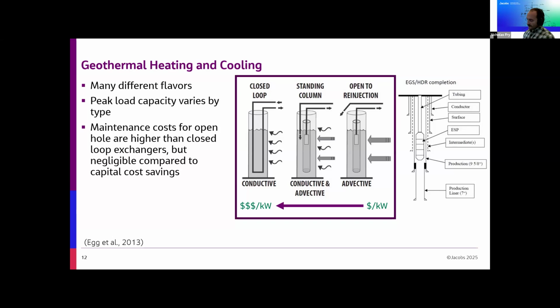Some differences: you may have casing in unconsolidated zones for geoexchange, but it's preferable that grouted completions, like the conductive borehole heat exchangers on the left side of the screen, are fully grouted from the bottom of the hole to the top. There are some open loop completions as well. What happens is the cost to the customer changes, which Delano, I'm sure, will elaborate on later. But closed loop geothermal systems, geoexchange systems, are quite expensive as an option.